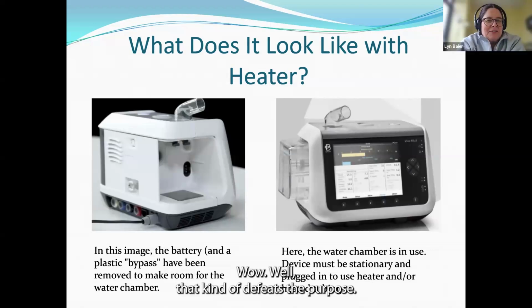And for further clarification, I was going to talk about this when I went over to the devices. Okay, so maybe we wait. Well, no, it's fine. This is a good time. The humidifier and the heated wire tubing do not work unless it is plugged into a household outlet. Wow, well, that kind of defeats the purpose. Yeah, the heating system in those draw a tremendous amount of power. The batteries could not support that. So if you're using the humidifier, you can leave the water chamber in there and you can leave the heated tubing on it, but it disables the heater functions when they're unplugged.